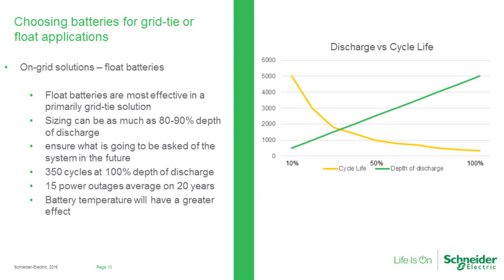Look over here on the right-hand side, we can see the discharge versus cycle life. You can see that green line going up is merely representing how far we're dipping into the batteries. You can see at 10%, gosh, look at that, we get almost 5,000 cycles. At 50%, we get right around 1,000. And at almost 100% depth of discharge, we're getting about 350 cycles. So when we do the math on that, 15 power outages on average for 20 years, that's only 300 cycles. So even with 15 power outages on average, the batteries are still going to age out before they cycle out.